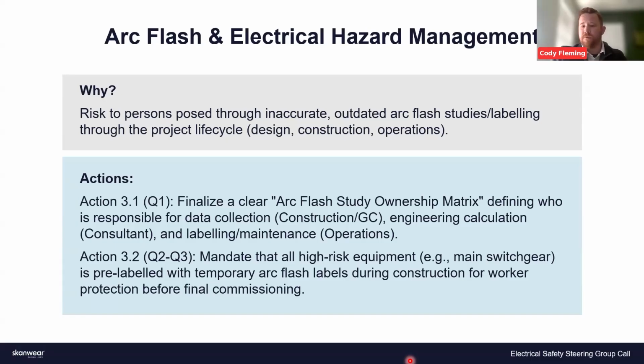The other concern is permanent equipment being fed by temporary power. The label is based off the eventual permanent feed. Yeah, absolutely, that should be accounted for. If you're going to use a temporary generator, you have to account for cable lengths, voltage rating, everything. So if you're going to be using a temporary system, you should have an engineering study done to accomplish the safety requirements for that temporary system.